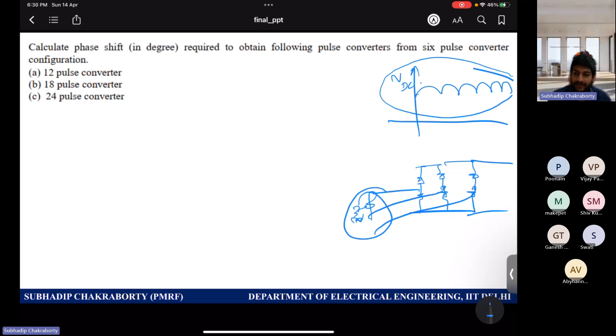As well as you could gain more control over the input side current. Because normally, with a diode bridge rectifier, it would draw non-linear currents, right? Agreed or not? If you plug in a three-phase supply with a basic three-phase uncontrolled 6-pulse rectifier to build these DC voltages, the current drawn from the AC side is very distorted. Agreed? Quasi in nature. If this feeds constant current loads at the DC side, the current taken from the AC side is purely quasi, square wave and quasi square wave in nature. Okay, I explained that to you.